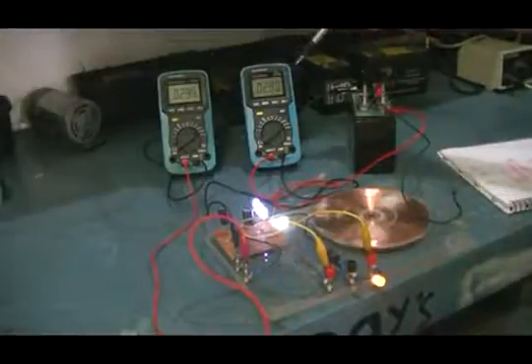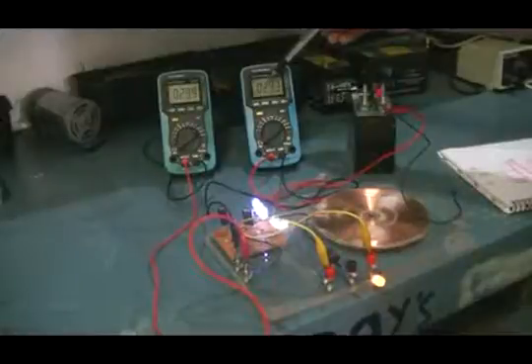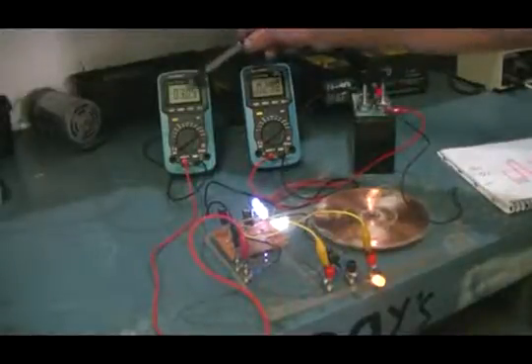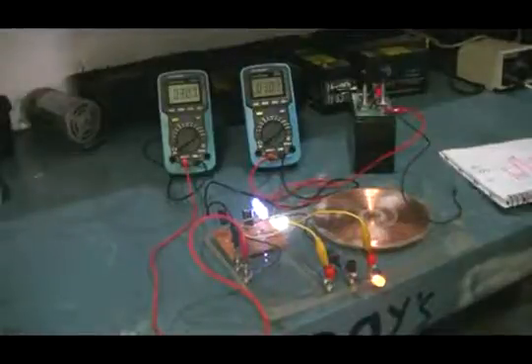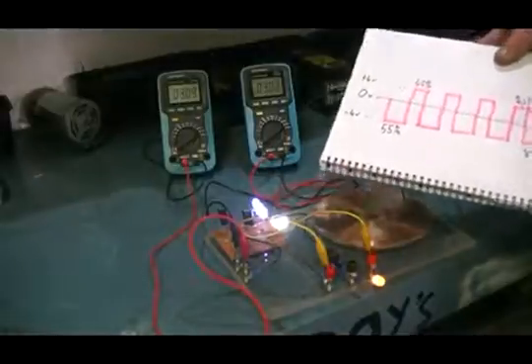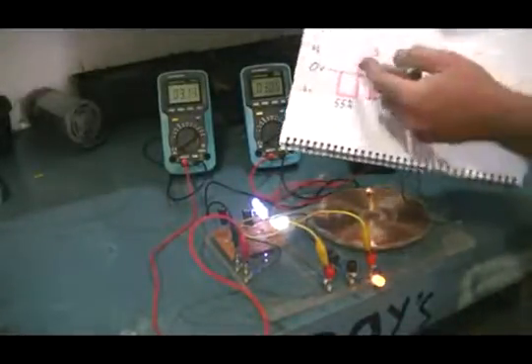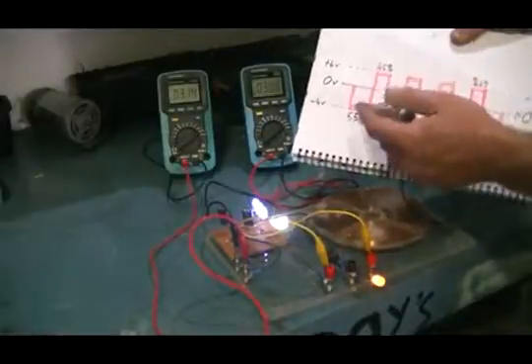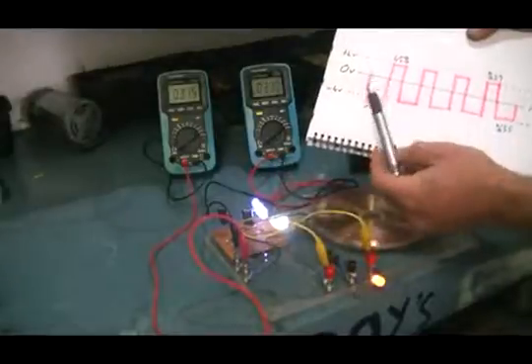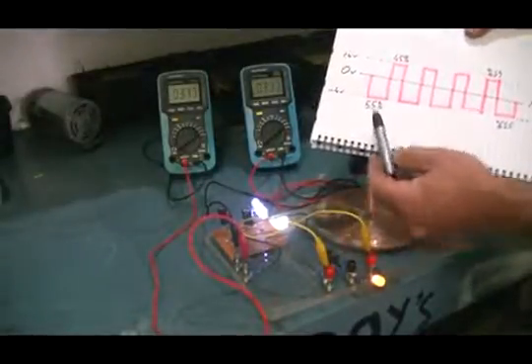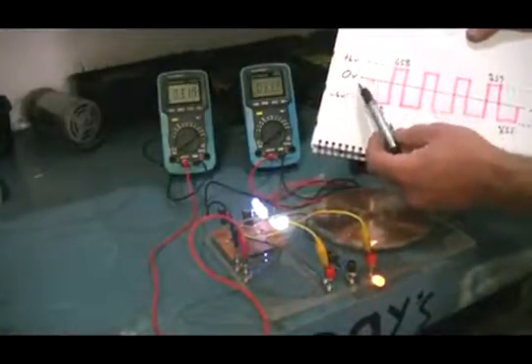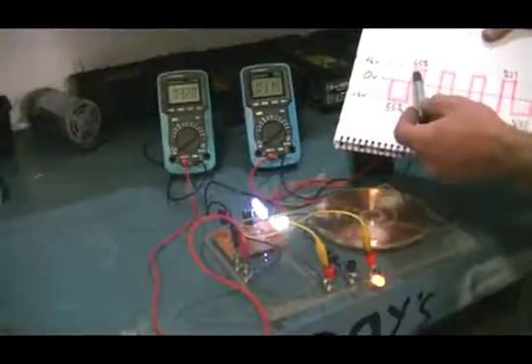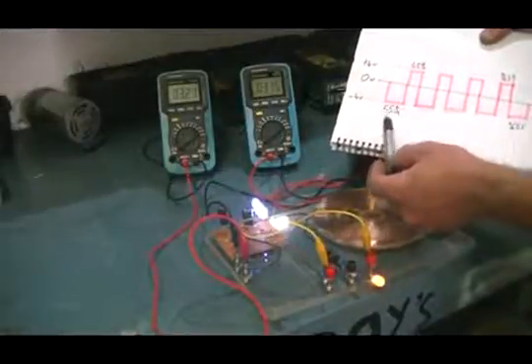Now, you will see at the moment on the positive output side we are putting in 2.94 milliamps and on the negative side we are putting 3.05 milliamps in. It seems that the high side of the square wave duty cycle is say 45% and the low side of the square wave is 55%, and these are just reference numbers to show the difference.